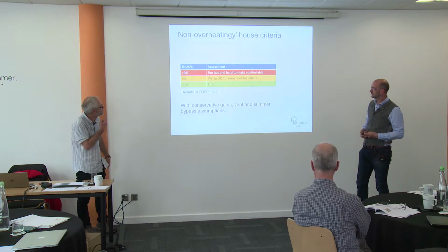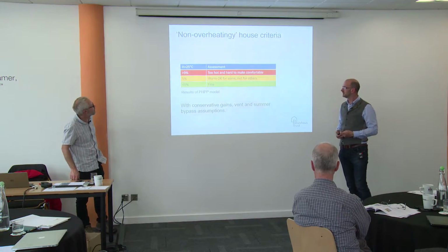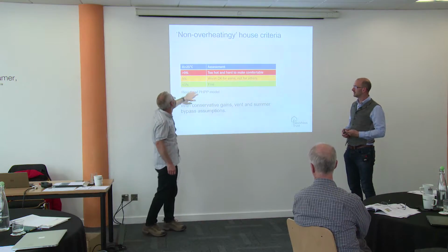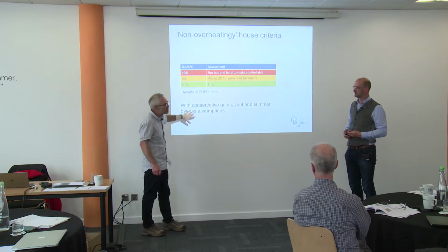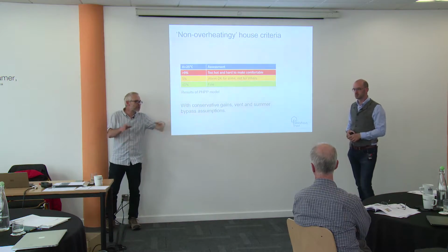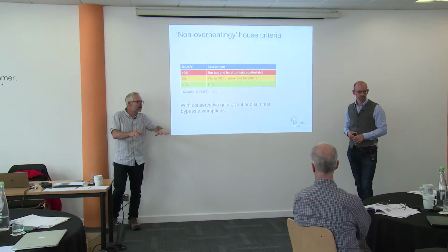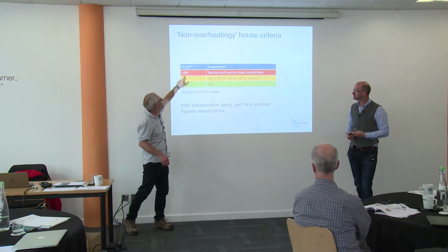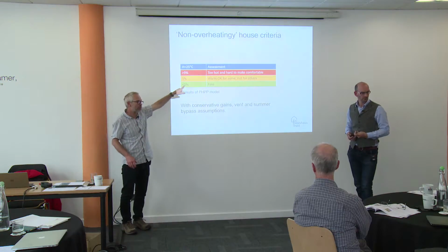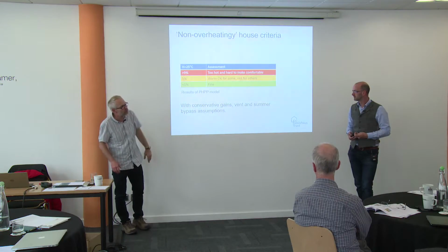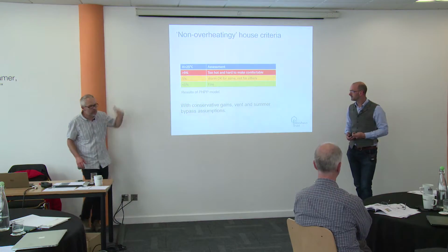So this is a slightly simplified version of the Passive House one. We're saying, look, less than 1%, again depending on the assumptions, is fine; 5% is okay for some, not others. So Ruth's, with the right assumptions, might be in that range. Lancaster is probably between the two. And then this one is too hot and hard to make comfortable. That depends on these assumptions, which are partly the ones we've given you on the handout. But we'll apply this to the case study.